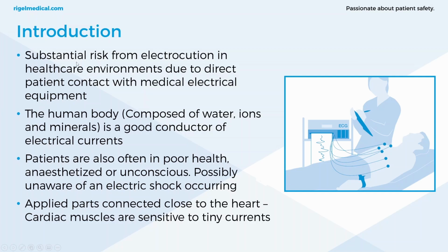Now, there is a further substantial risk from electrocution in healthcare environments due to the direct patient contact with medical electrical equipment. The human body is composed of water, ions and minerals, and it's a good conductor of electrical currents. More than 99% of the human body's resistance is in the skin, and that's why it's considered a really good barrier to electricity, unless, of course, it's wet, then that resistance is reduced.